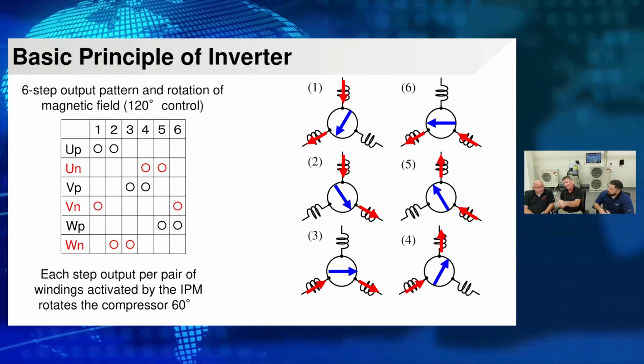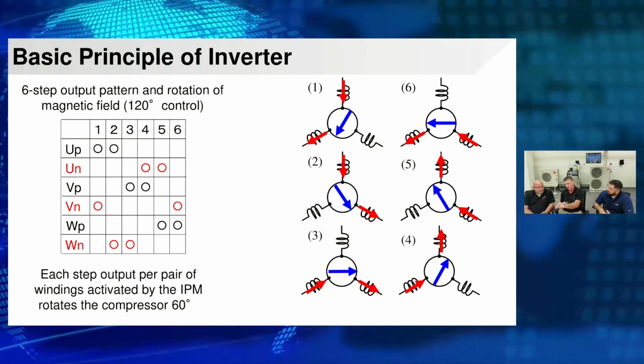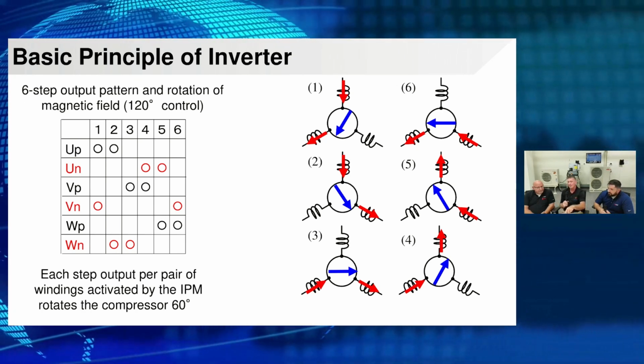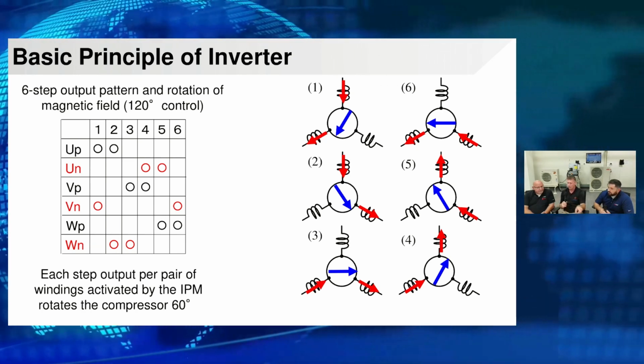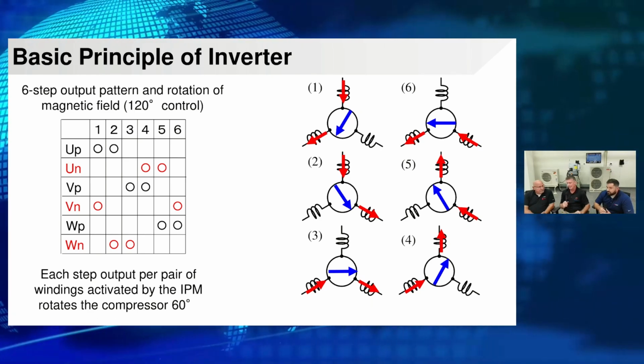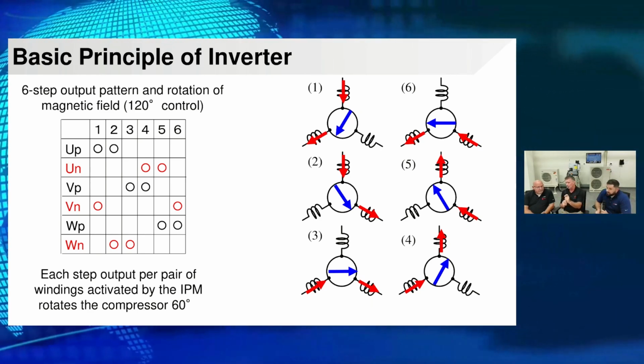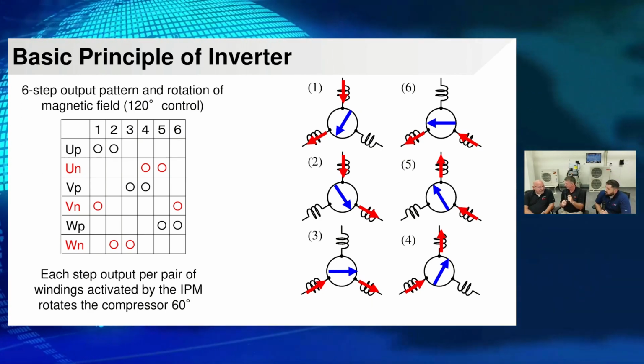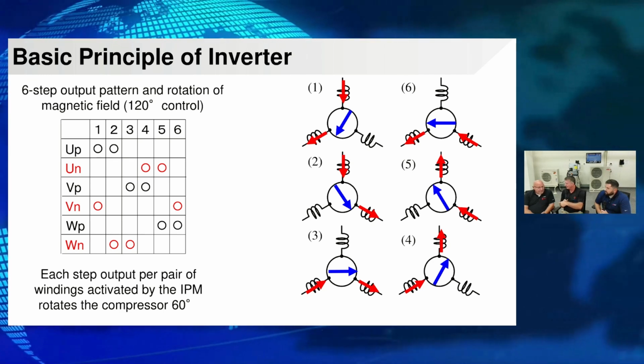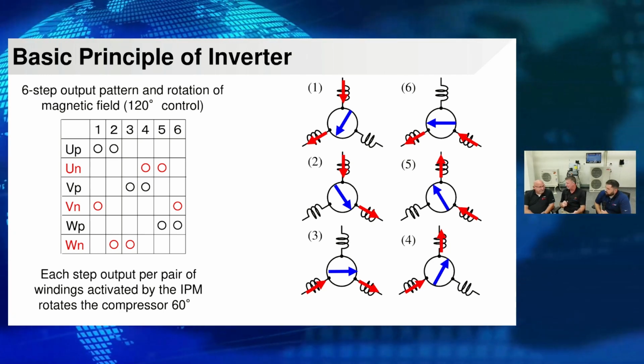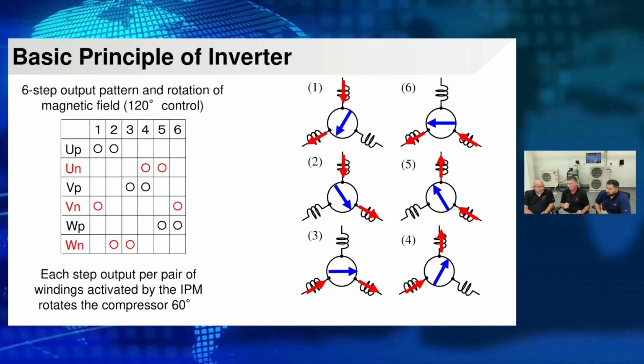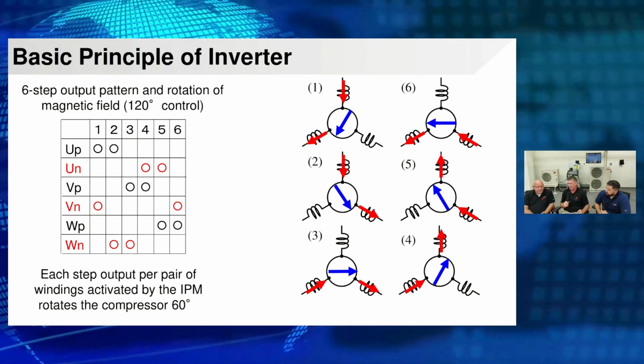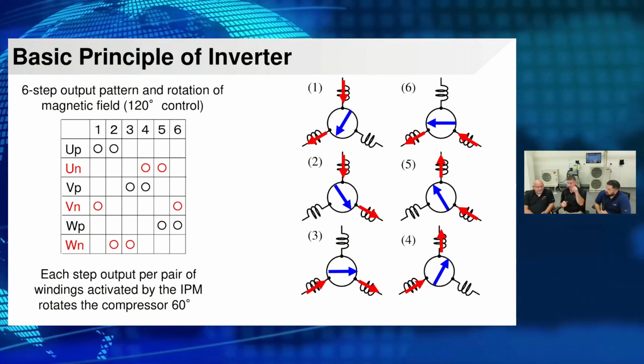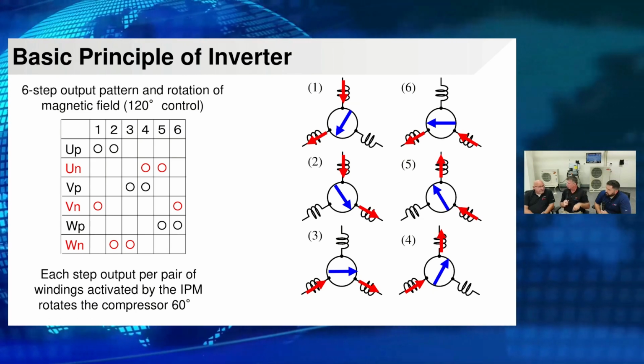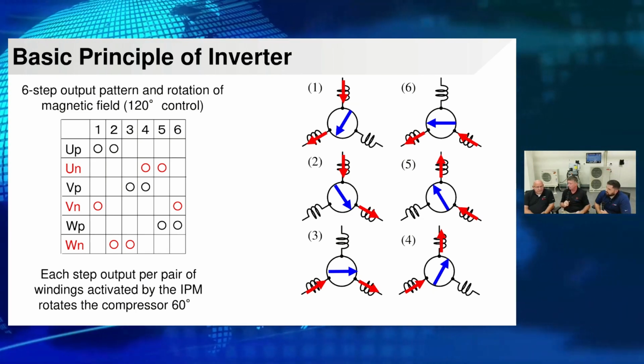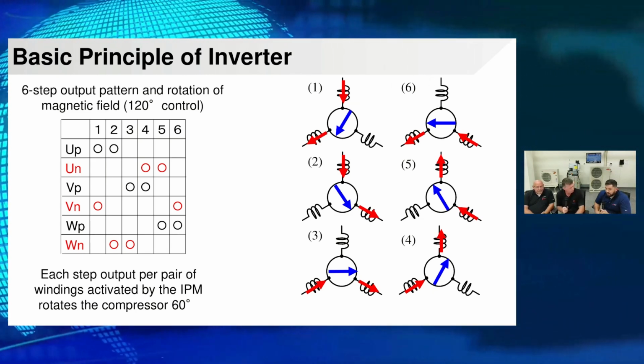In this exact rotation, if we look at number 1 and we're applying power to the IGBT through the top and through the left, the 2 red windings, that means we have the potential to produce a little bit of voltage on that additional winding, which is actually our back EMF. So this is a really good diagram to explain what back EMF is and how it's reading, but it's got to read just as fast as we're applying - there's a lot to calculate in that processor.